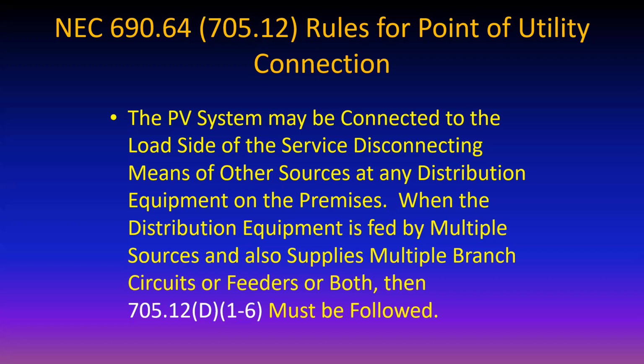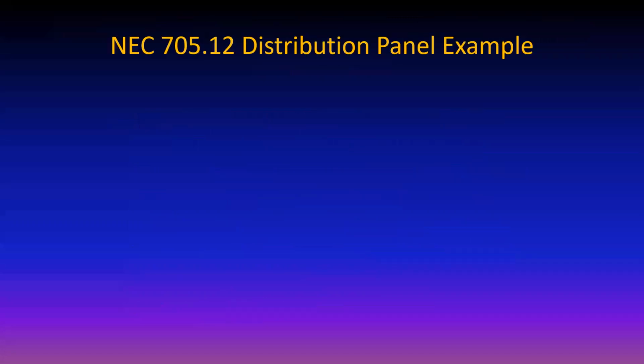All right, and this was a blessing when that finally came out, because there was a lot of confusion up to this point about exactly what's okay and exactly what's not okay. But 705.12 in the National Electrical Code now, and especially in 2020, if your jurisdiction is using 2020, makes it very clear about all kinds of oddball ways you might tie into the utility, depending on exactly how that distribution system comes in from the meter.